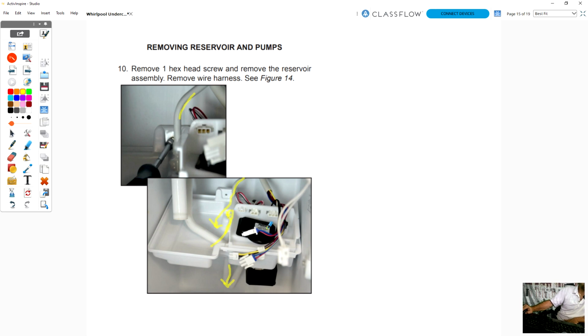So the top piece here is our recirculation pump, and that recirculation pump runs through this white hose and goes up to our distributor on top of the evaporator, and then it flows back down into here and returns back here. This one on the bottom is our drain pump.